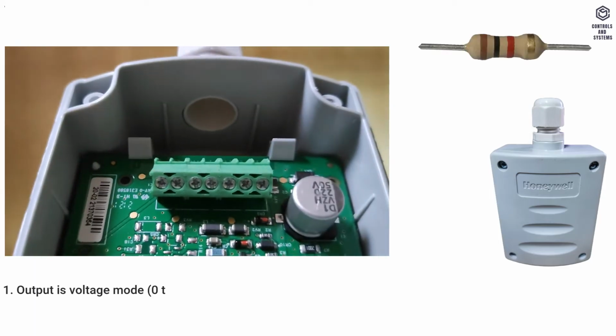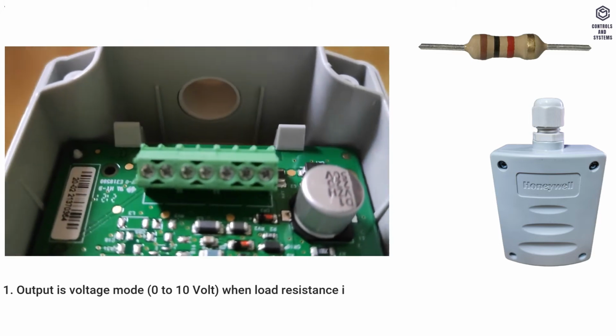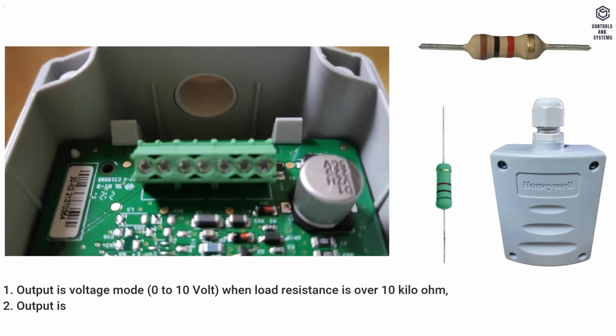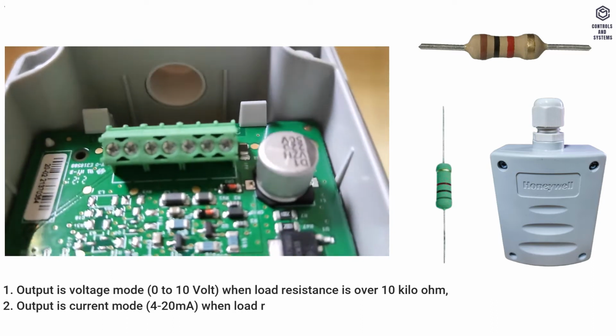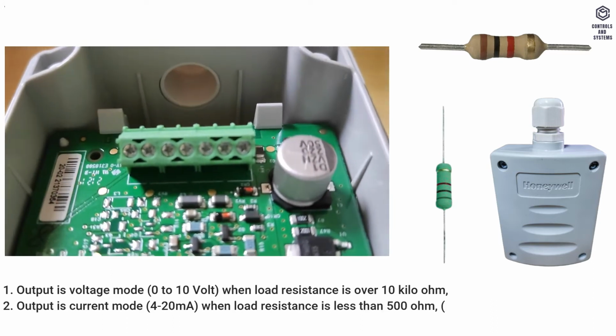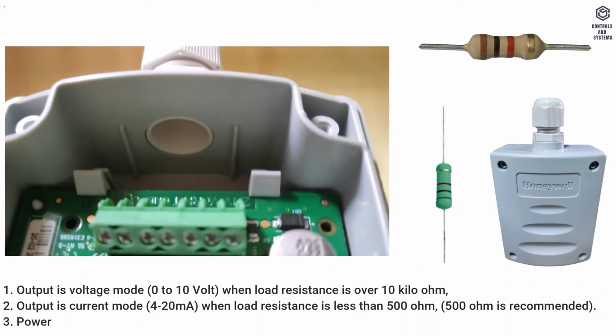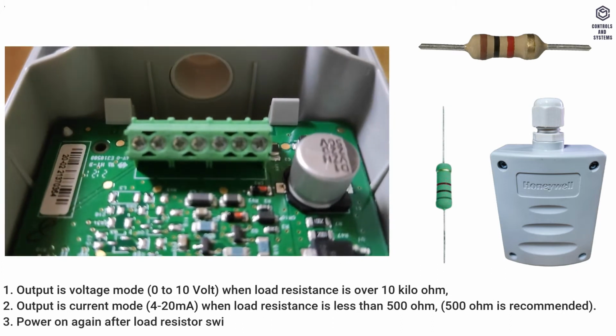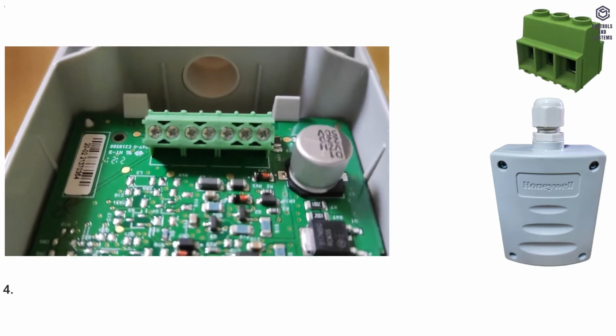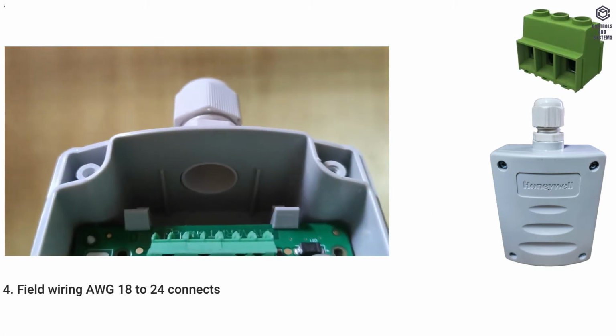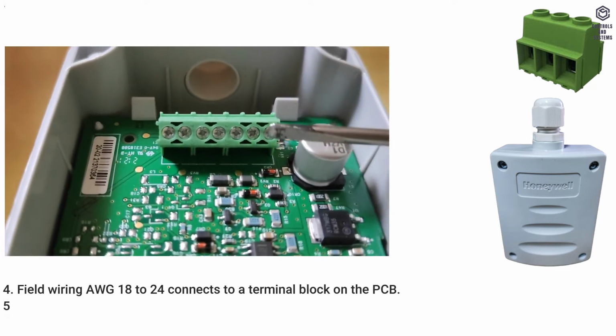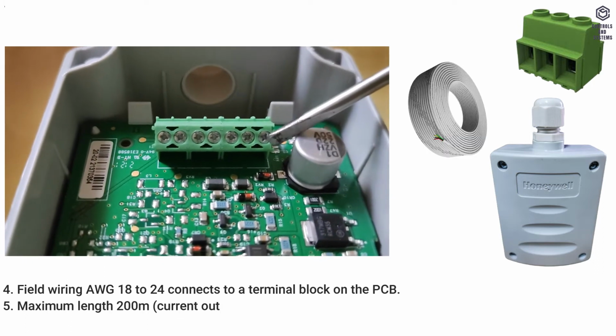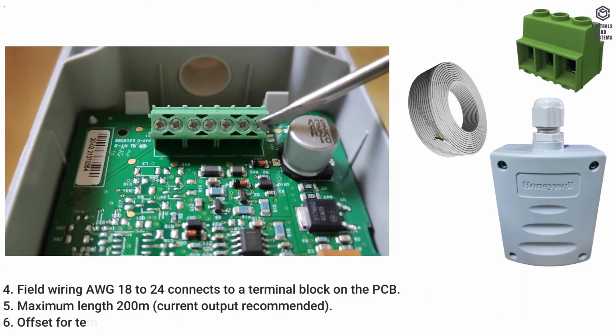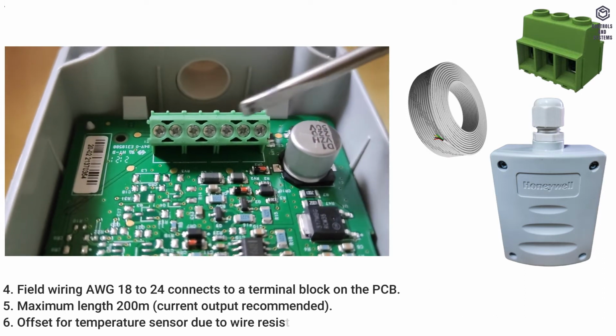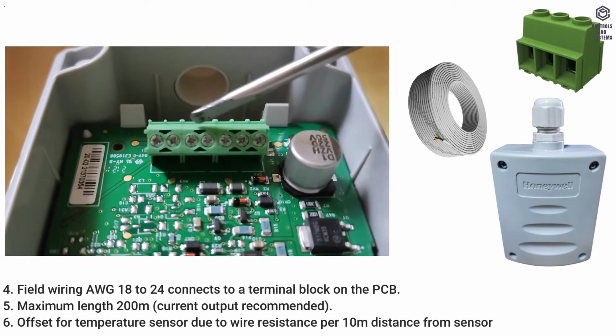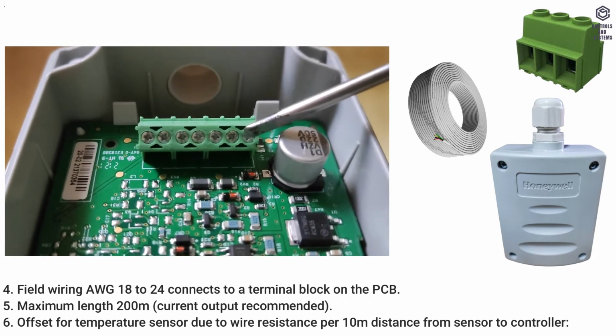1. Output is voltage mode, 0 to 10 volt, when load resistance is over 10 kilo ohm. 2. Output is current mode, 4 to 20 milliamperes, when load resistance is less than 500 ohm; 500 ohm is recommended. 3. Power on again after load resistor switch. 4. Field wiring AWG 18 to 24 connects to a terminal block on the PCB. 5. Maximum length 200 meters, current output recommended. 6. Offset for temperature sensor due to wire resistance per 10 meters distance from sensor to controller.